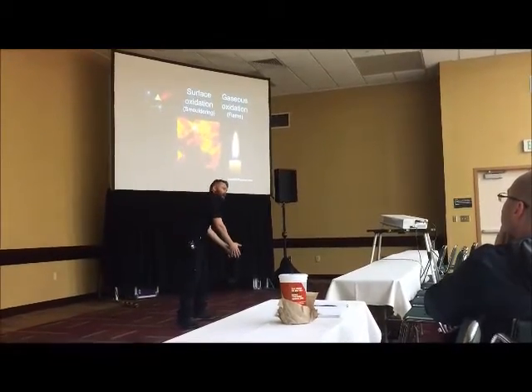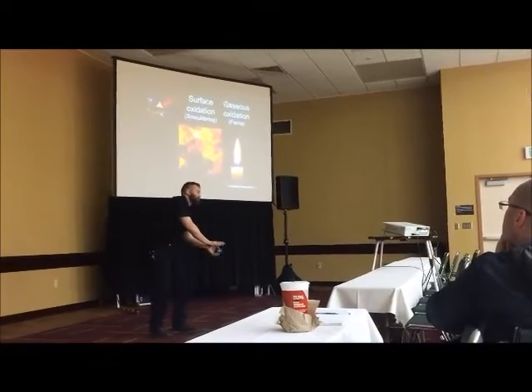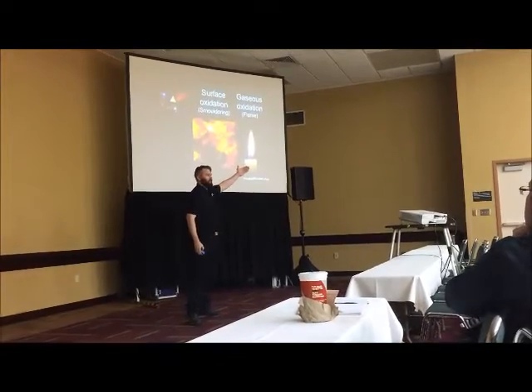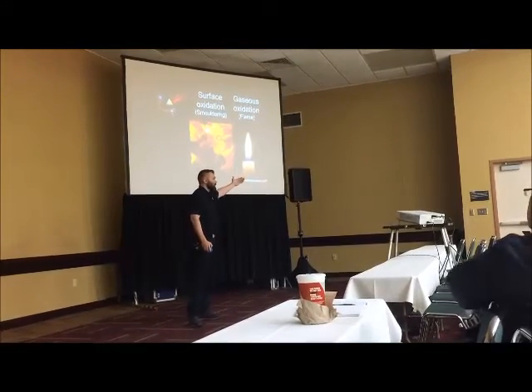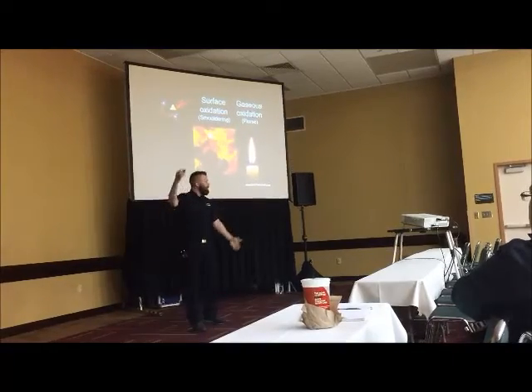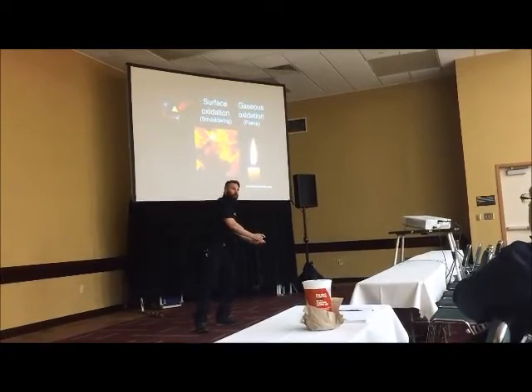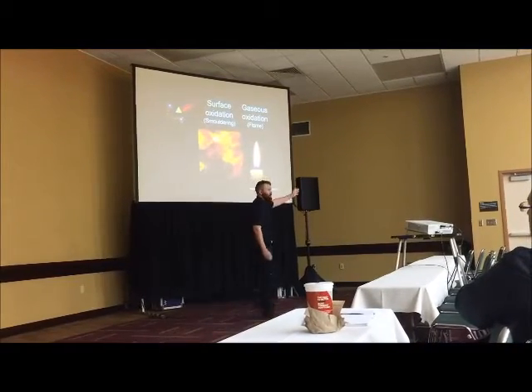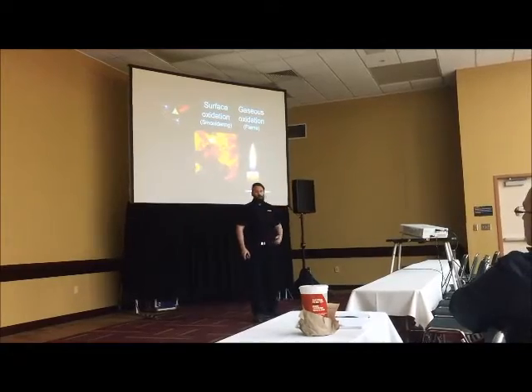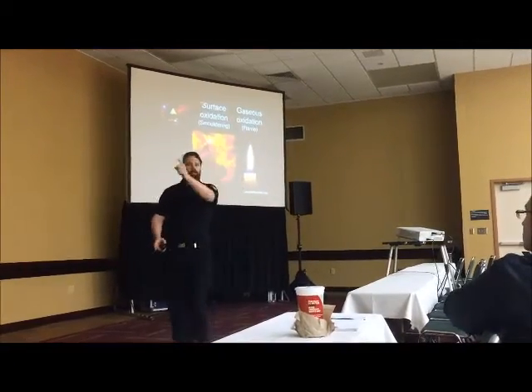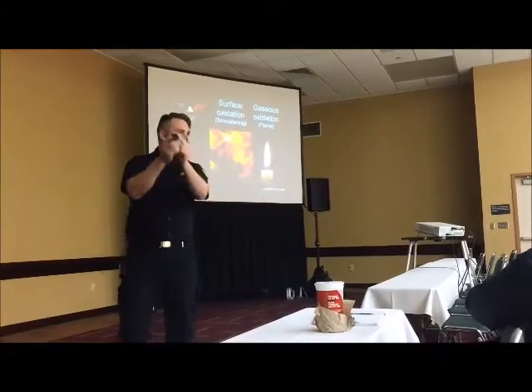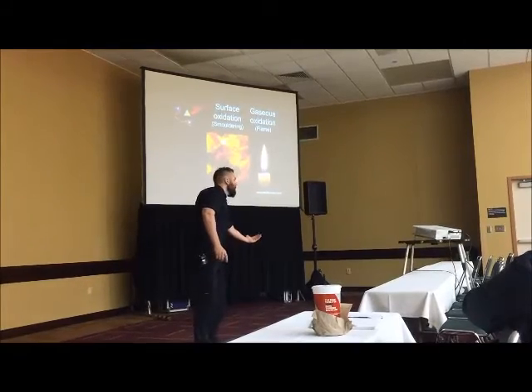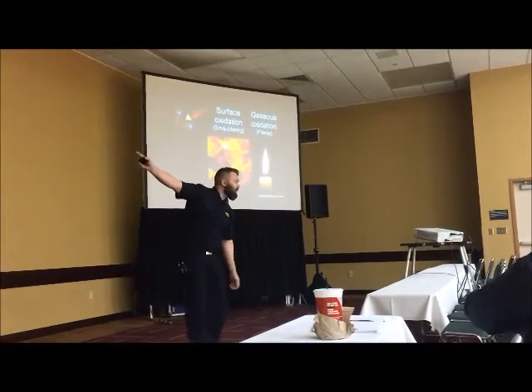The oxygen needs to go all the way down to the fuel because the fuel is actually sitting stuck at the surface. In most cases we talk about cellulose-based carbon fuel. You have to get the oxygen all the way down so that the oxygen meets the fuel and can oxidize. But with flaming combustion — gaseous oxidation — the fuel can travel wherever it wants until it finds oxygen and enough heat to start oxidizing, and that can happen at the source or on the other side of the building.